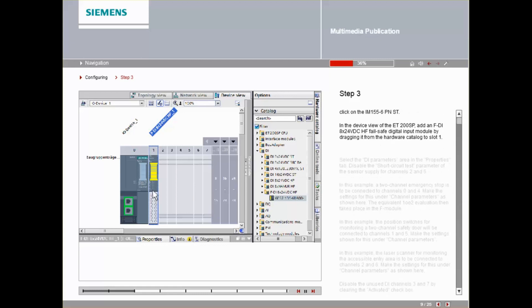Select the DI parameter area in the Properties tab. Disable the short circuit test parameter of the sensor supply for channels 2 and 6.